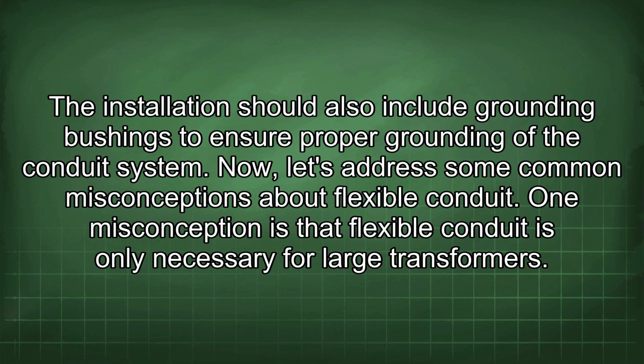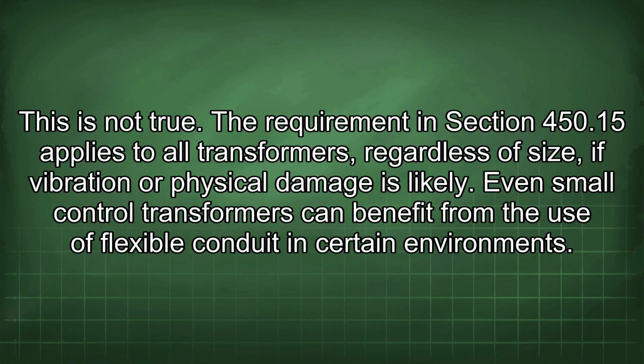Now, let's address some common misconceptions about flexible conduit. One misconception is that flexible conduit is only necessary for large transformers. This is not true. The requirement in Section 450.15 applies to all transformers, regardless of size, if vibration or physical damage is likely. Even small control transformers can benefit from the use of flexible conduit in certain environments.